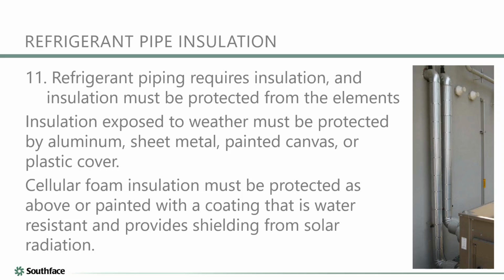And the next one here, a pretty standard requirement for refrigerant pipe insulation. We need to have it. It needs to be at a specific R value, and most important, and I think most often forgotten, it needs to be protected from the elements. So we've all been on roofs and seen that foam insulation even after a few months, it just deteriorates to nothing once it gets to the elements. So that's something that we really need to see more of, and it's a requirement in this part of the code. So any good stories of deteriorated insulation or anything like that?